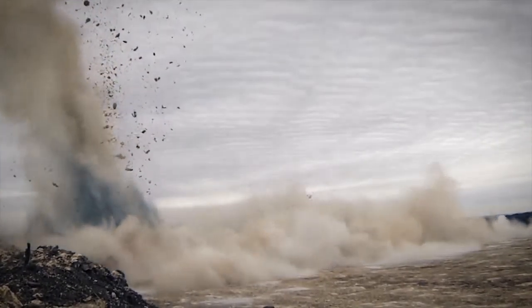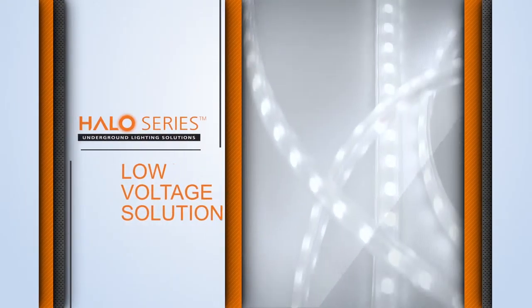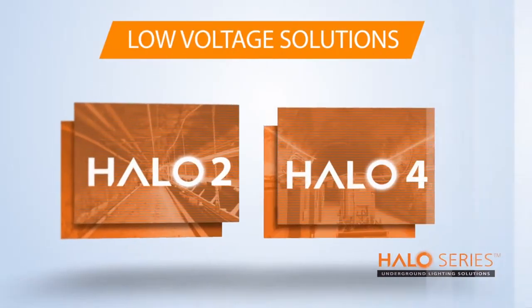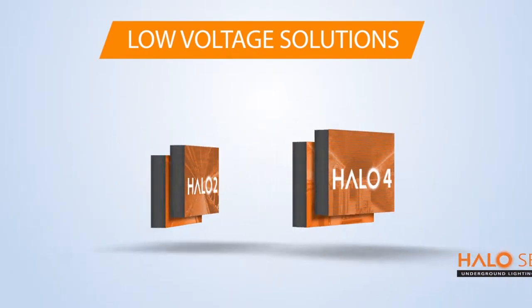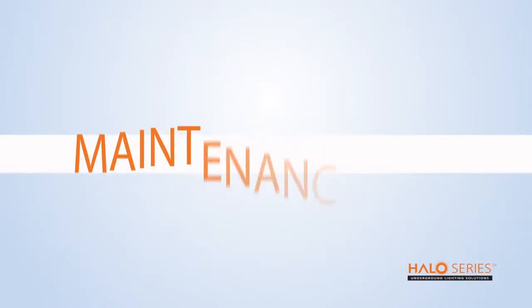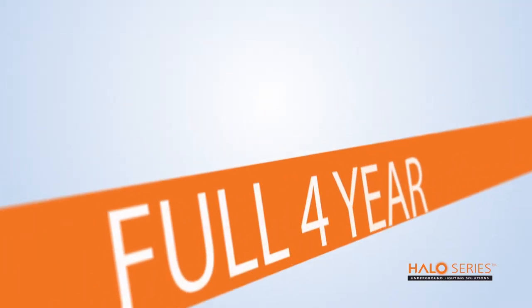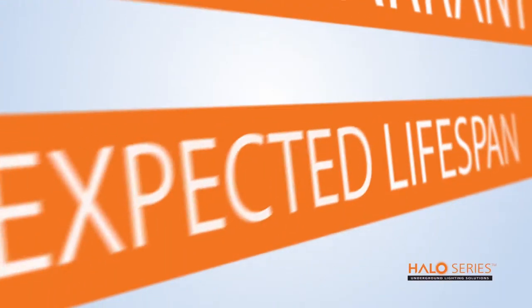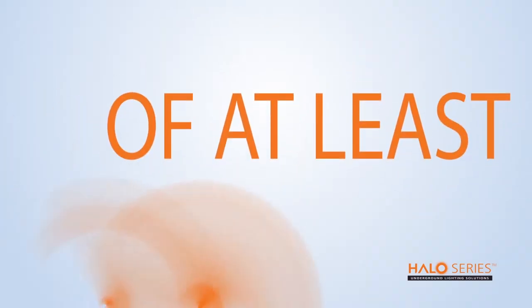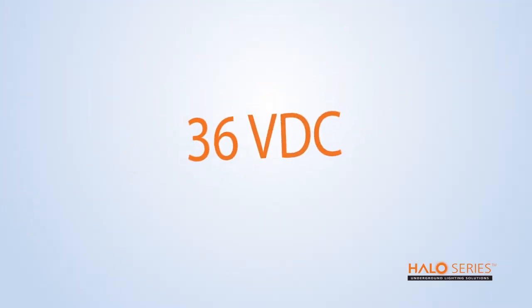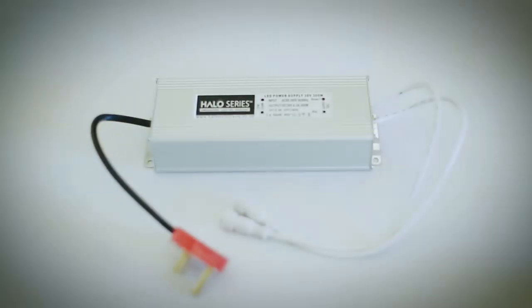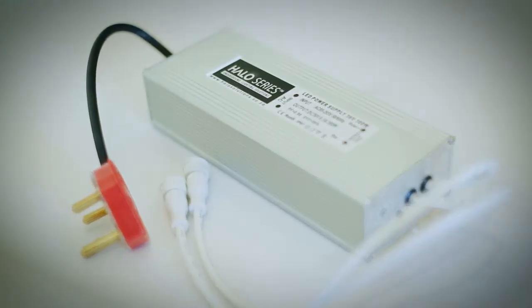Halo low voltage solutions, incorporating Halo 2 and Halo 4. The low voltage solutions are maintenance free lighting solutions with full 4 year warranty and an expected life span of at least 10 years. The available voltages are 12 volts, 24 volts, and 36 volts DC. The lighting strips are energized by means of a power controller.